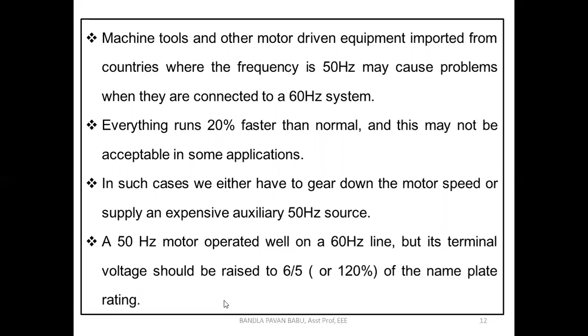Next, a 50 hertz motor operates well on a 60 hertz line, but its terminal voltage should be raised to 6/5 or 120% of the nameplate rating. If you want to utilize the 60 hertz line, we need to increase the voltage to 120%, so 20% extra. You are familiar that if we increase the voltage, the torque also gets increased. So that should not happen.